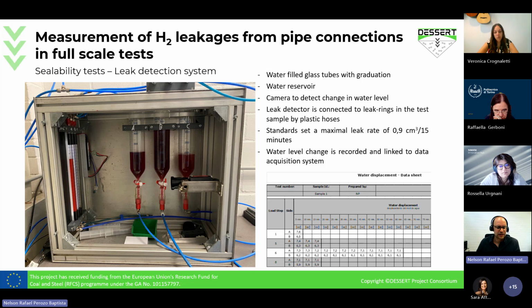As the standard requires, this level change has to stay below 0.9 cubic centimeters in 15 minutes. So what we do is fill a protocol in which we measure the change in level, or the value of the level, every 5 minutes. This is what you find here.